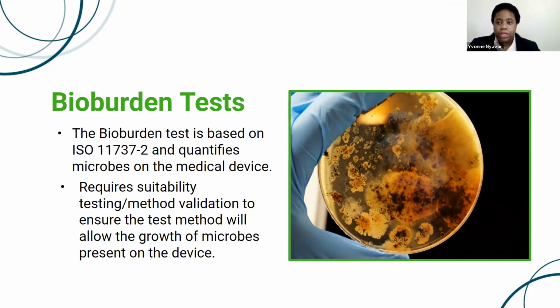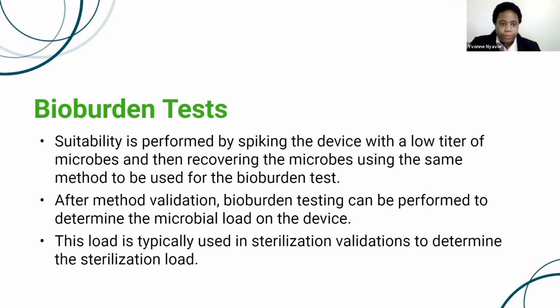And so we will typically spike a low load of 6 different microbes that are named in USP 61, and then try to recover their growth from the device, just to make sure that the device isn't preventing the growth of the organisms of interest. So bioburden test suitability, just as I mentioned, we are spiking and then recovering using the exact same method we would use for the actual test.